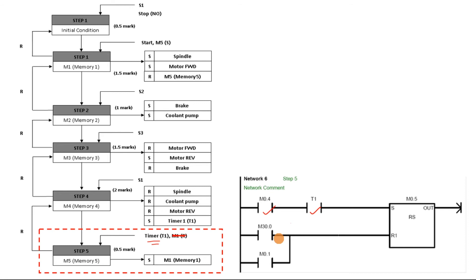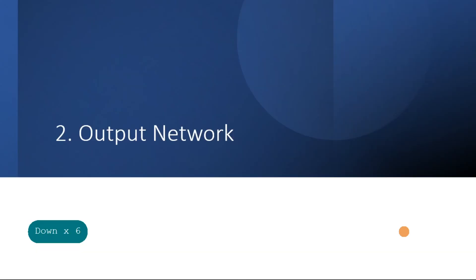That is how you translate the step sequence using memory. You just translate using the input conditions — the input conditions can come from sensors as well as the memory step. You have two inputs: the first one is for set and the second one is for reset. After you have done the step sequence network, only then can you move to the output networks. The output network will hold all the output conditions of each step.